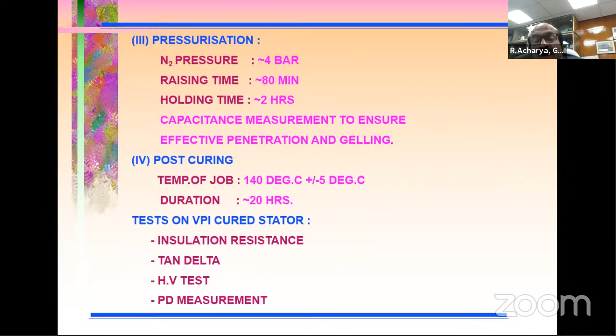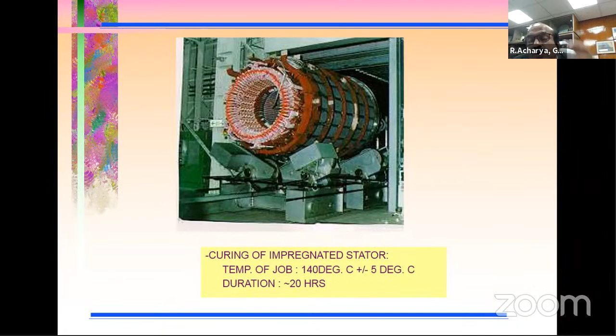There are a lot of quality checks that are made, and the job is taken out and put inside a furnace. In the rotating condition, the entire thing is cured in a furnace at 140 degrees Celsius for almost 20 hours. So the entire thing becomes a solid monolith. Unlike the previous kind of design wherein individual coils are impregnated and insulated and then put, the entire job is impregnated along with the core and the winding and then all the support system.